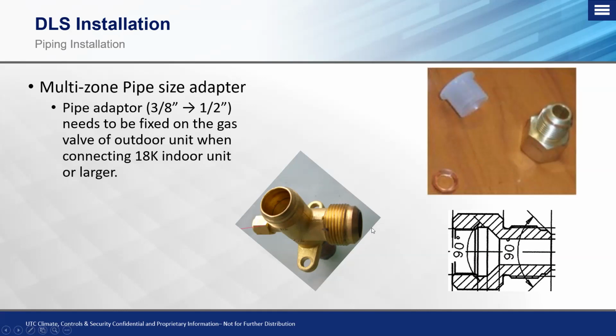If you don't put this in here and you just put this straight on, you don't have anything sealing that refrigerant from leaking out, and it will leak out at a very fast rate. So it's important to make sure that we take this copper fitting here and we put this inside the adapter when we tighten on the service valve fitting.